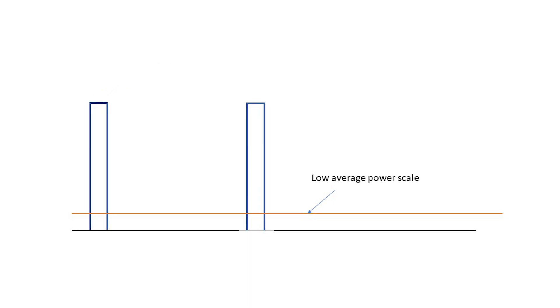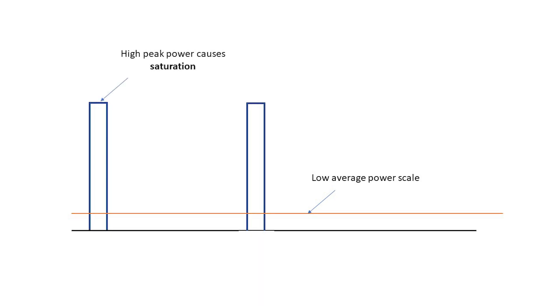If we choose a scale appropriate for the average power, as we normally do when measuring power of CW beams, then we're looking at a low average power scale, meaning high gain in the electronics. But then, when the pulses come, the detector will momentarily saturate, which can lead to a measurement error.